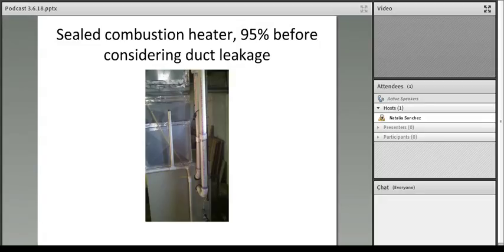And why do we do this? Because if we spend a whole lot of money on a 95% efficient furnace, what's known as AFUE, 95 AFUE for this gas furnace, we want to get full utilization of that energy. Duct leakage is not like water leakage. We would find a water pipe leaking, hopefully. It's really hard to find air leaking out of ducts. So we've got to go look for it specifically, fix it, absolutely, to make sure the air that we're buying, or the fuel that we're buying to create hot air, gets into our rooms. Right. And the return side is the air from the house going back to the heater to be reheated. Right. And no disconnect in that loop as much as possible.